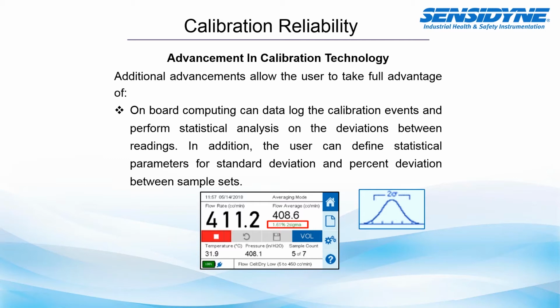Typically, I like my individual samples to be under 2.5%. I've seen where you're using a cyclone device that you want more accurate. You may set that at 2% or even as low as 1% requirements. But generally, readings under 2.5% are going to be acceptable. The reason why I choose 2.5% is if the variation was as much as 2.5%, you could have a plus or minus 5% error from your start and your stop reading, which is, remember, the percent deviation that we want between our pre and post calibration.